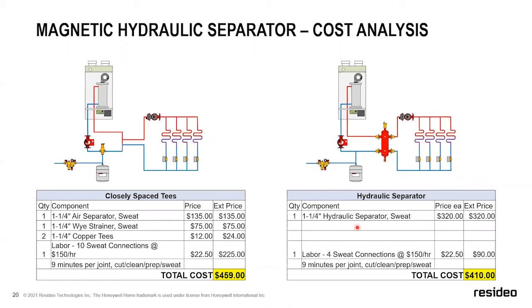So let's look at this same example with a 1.25" hydraulic separator. Yes, the cost is absolutely more expensive compared to what we're looking at over here. However, you only have 4 connections now. You don't need the air eliminator anymore, the SuperVent, because this is going to take care of that. So now you're looking at 4 connections, which dramatically reduces the time to install as well as the cost associated with it. So now you're looking at $400 instead of $459.